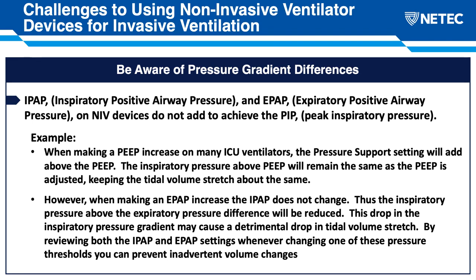So if I had an IPAP, the inspiratory pressure, of 10 and an EPAP of 5 set, and my patient wasn't oxygenating well enough and I needed to go up on the bottom, on the EPAP, if I went from the EPAP up to 10 and my IPAP stayed at 10, my total airway pressure is only 10. I'm no longer ventilating and I don't have a pressure gradient there. So it's just something to watch anytime you're making pressure changes on a non-invasive device, to make sure you're achieving the volumes and the pressure gradient that you were hoping for.